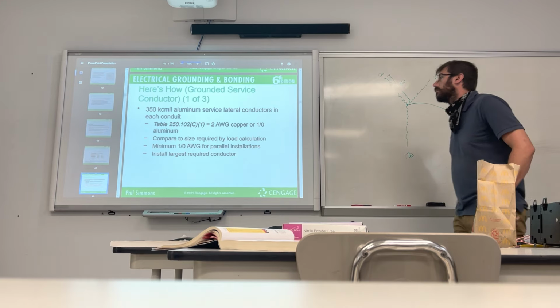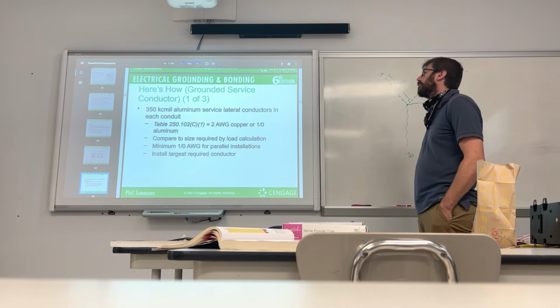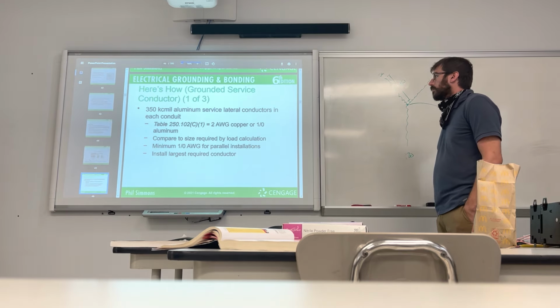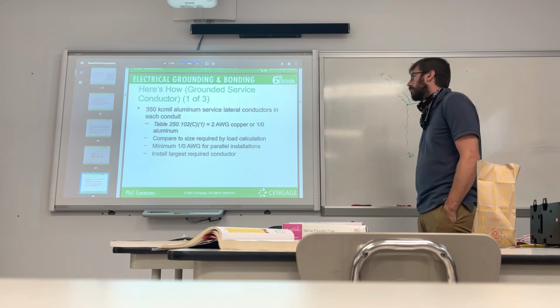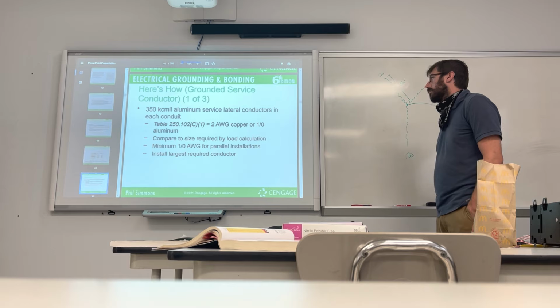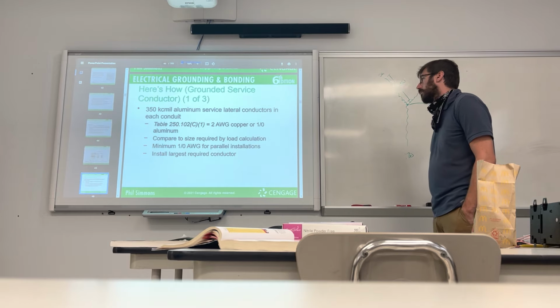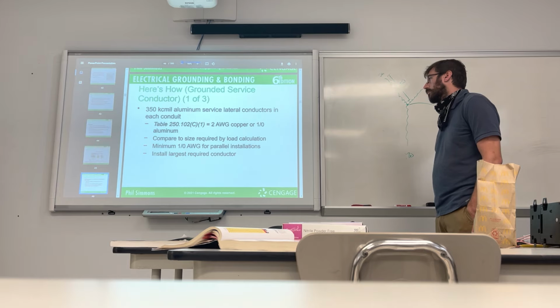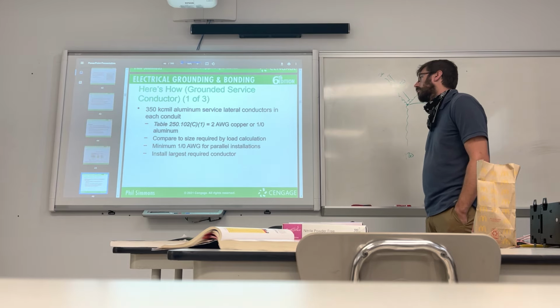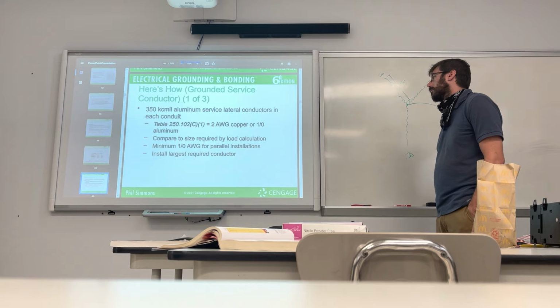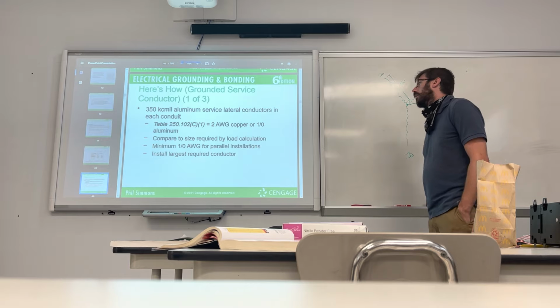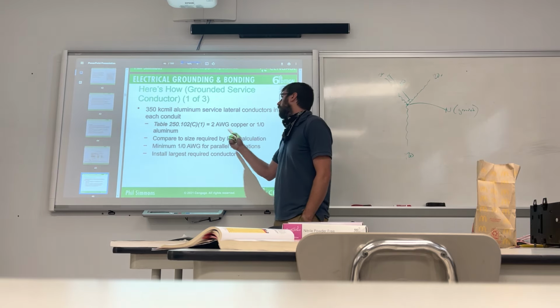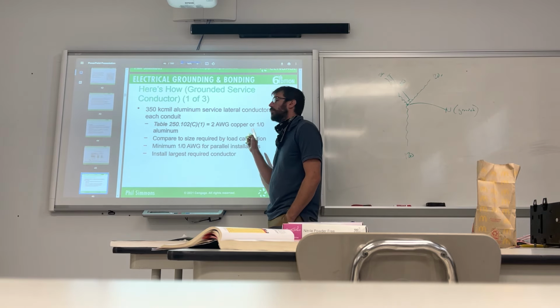Here's how. Ground service conductor. 350 kcmil aluminum service lateral conductors in each conduit. Table 250.102(C)(1) equals 2 AWG copper or 1 aught aluminum. Compare the size required by load calculation. Minimum 1 aught AWG for parallel installations. Install the largest required conductor. So now, once again, 2 gauge or 1/0.